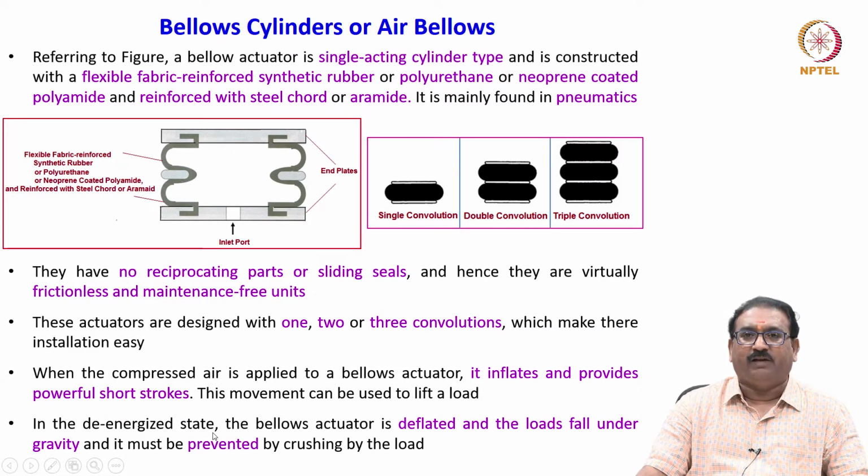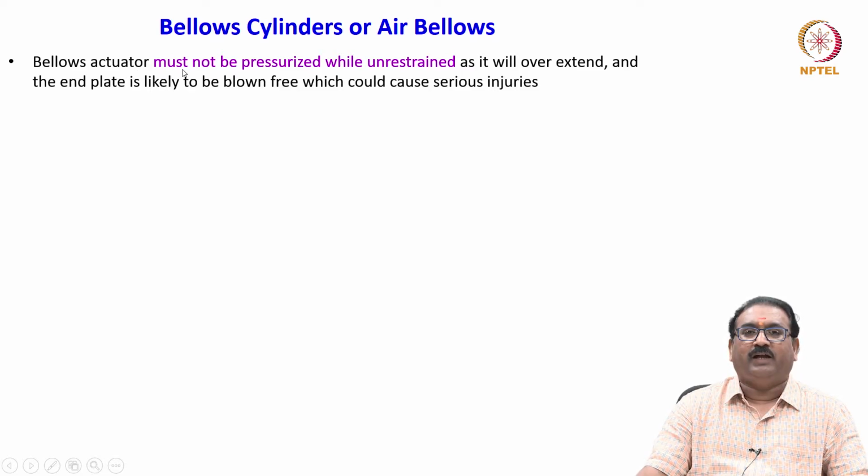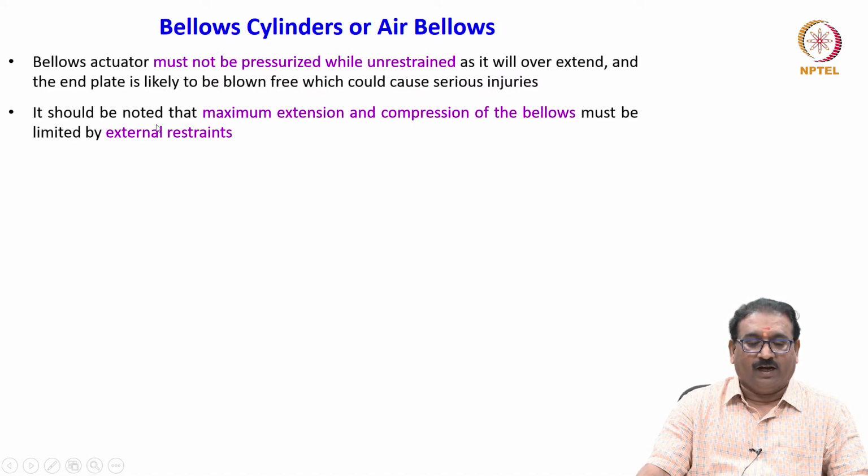In the de-energized state, the bellows actuator is deflated and the load falls under gravity, and this must be prevented from crushing by the load. Bellows actuators must not be pressurized while unrestrained, as they will overextend and the end plates are likely to be blown free, which could cause serious injuries. It should be noted that maximum extension and compression of the bellows must be limited by external restraints.